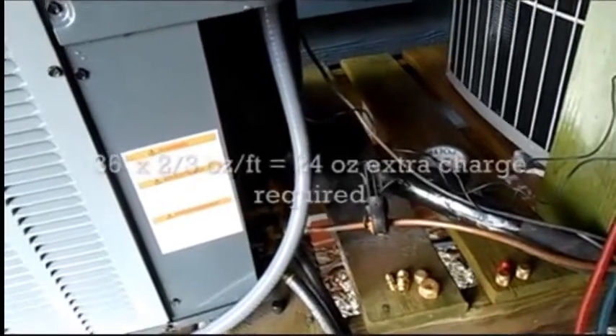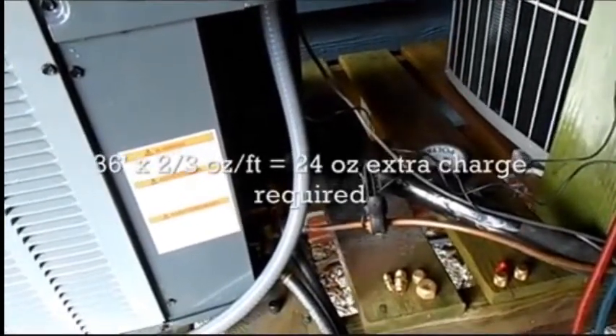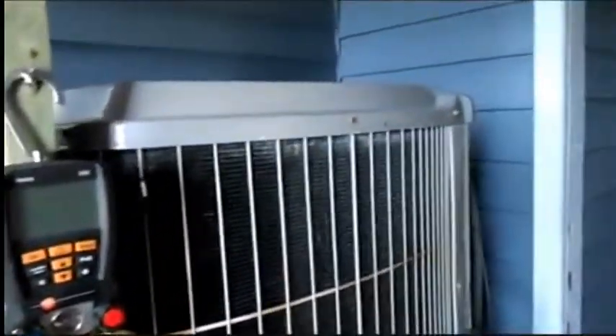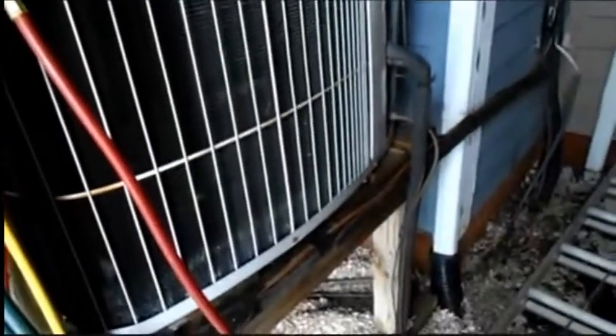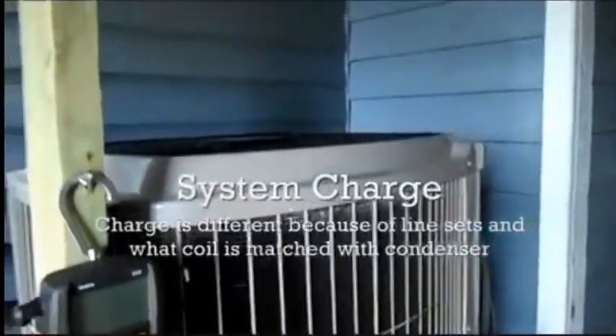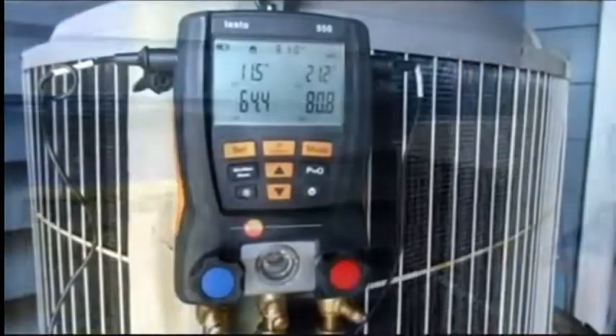So we have 35 feet. Let's say that's 36 feet. You're looking at 24 ounces, so I'll probably end up putting 20 in just to make sure, because the system charge isn't always what it says. Sometimes it's more, sometimes it's less, I've noticed over the years. You think it'd be the same, but it's not always the case.